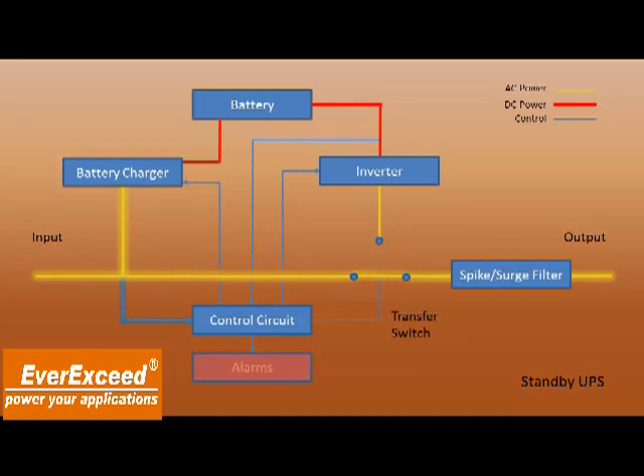Powering this up, we'll see that we end up with power to the battery charger and going through the filter at the end and to the output. We have an alarm set because the battery is discharged. We're showing a discharged battery alarm. The control circuit will turn on the battery charger which sends power to the battery. When the battery has charged up, it sends out power to the voltage and tells the control circuit which is able to shut off the charger.